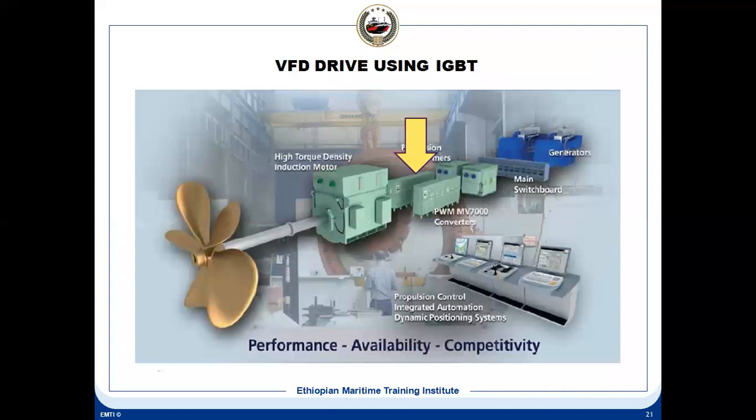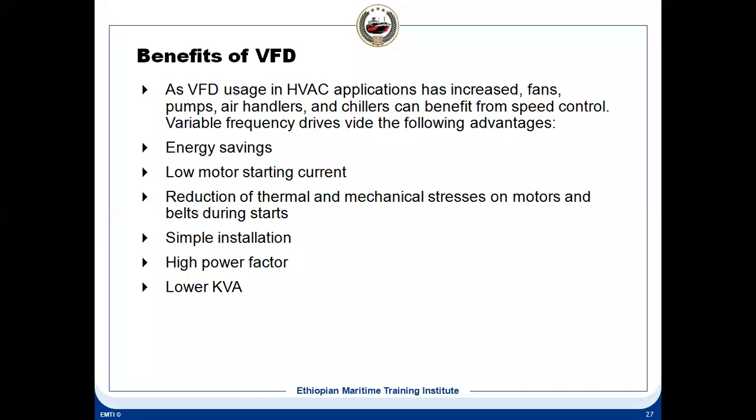You want to save energy depending upon the seawater temperature or your requirements. So based on the seawater temperature, the energy can be saved if you have a variable speed pump. You can reduce the voltage you are giving to a pump motor, and basically you save energy in that. So the applications are plenty. It is not that VFD is used only for propulsion drives or anything. It is used everywhere. The main purpose is energy saving.